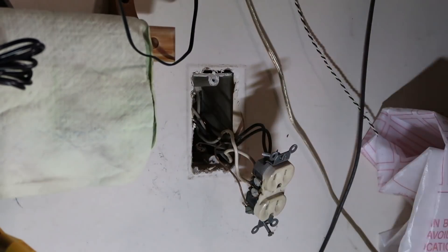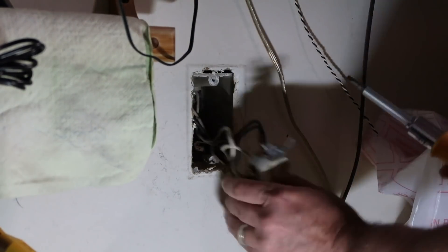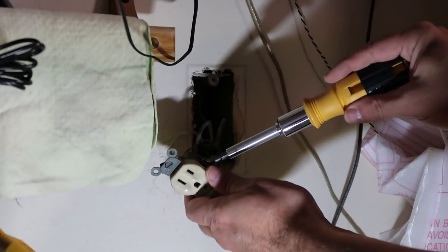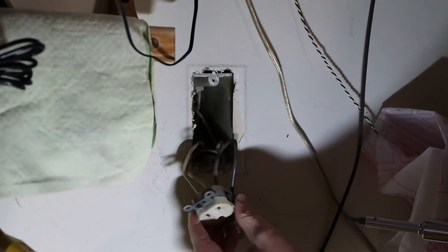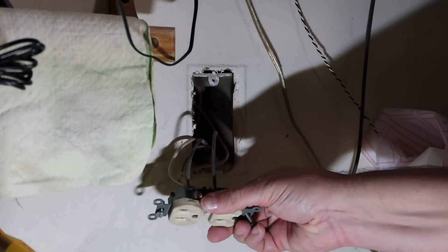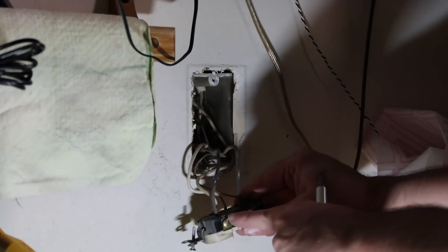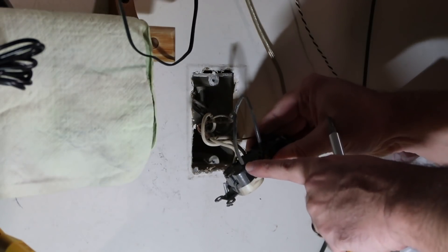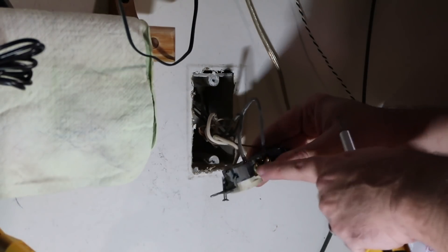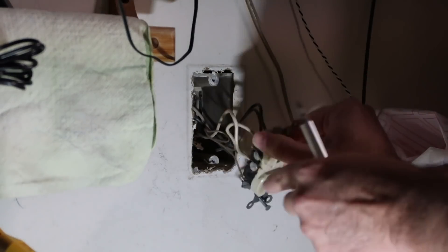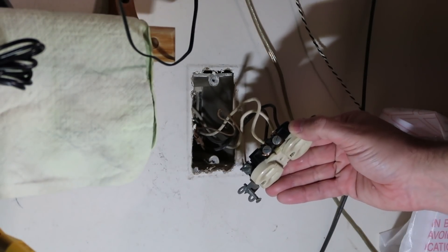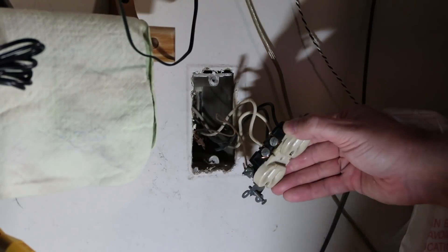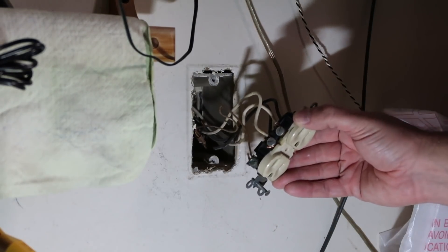So now we verified that's the case. They didn't switch it at the breaker box, which they shouldn't have. Now we can unscrew these screws and take the wires off of the outlet. And then we can wire them up to our new outlet. So let's go ahead and do that. I'm going to try to do this without getting in the way. So interesting. They stabbed the back of the outlet, as you can see here, with the black wires, like I mentioned before. But they screwed the white wires to it. No big problem.